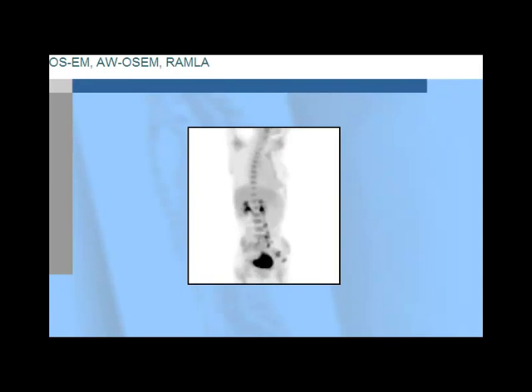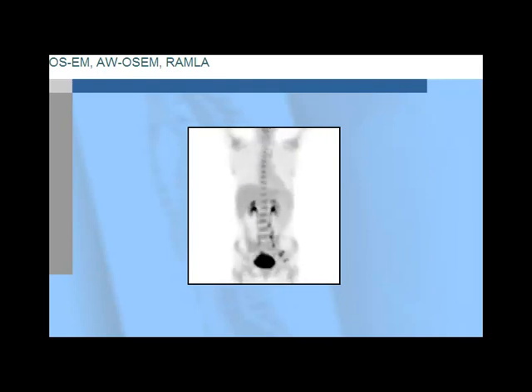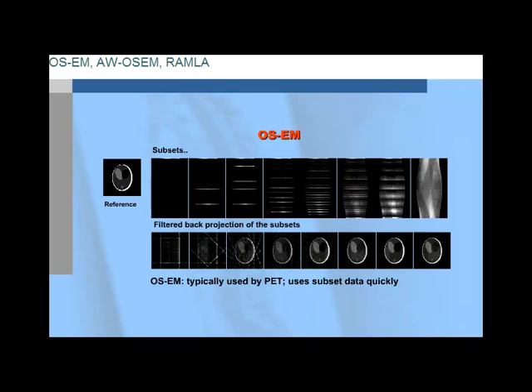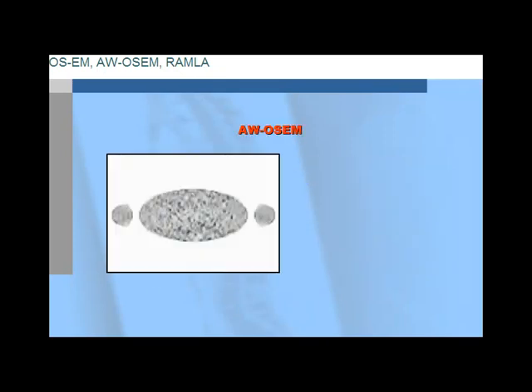In this final section, we'll explore some of the other reconstruction methods that are commonly used for PET. The most important point is that different PET programs utilize different methods for reconstructing image data, so having a general grasp of each one may be useful. We will begin with Ordered Subset Expectation Maximization, or OSEM. PET typically utilizes this technique to reconstruct images. OSEM employs an EM method; however, it only uses a subset of the projection data in the forward projection step. Since calculating an update to the image involves only a fraction of the complete data set, it takes only that fraction of the time the full EM algorithm needs. Our next option is attenuation-weighted Ordered Subset Expectation Maximization, also known as AWOSEM.